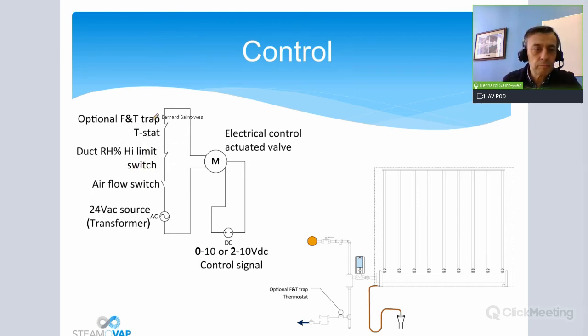And then you have the optional float and thermostatic steam trap thermostat. So all this can be put in series. Those two usually are normally closed, so it's always closed, and it will open in case the temperature is going too low or too high. Too low in this case, or humidity going too high in this case. The airflow switch, usually it's normally open, so it's open when there is no air, closed when there is air movement in the duct. All this will be in series on the 24 volt line source, basically a transformer.